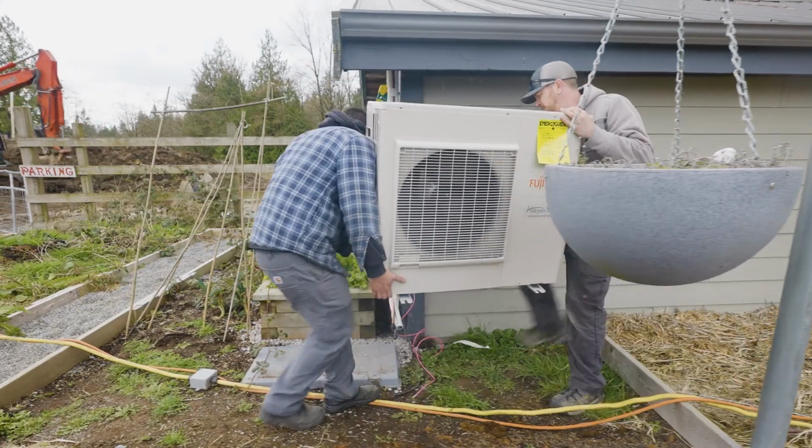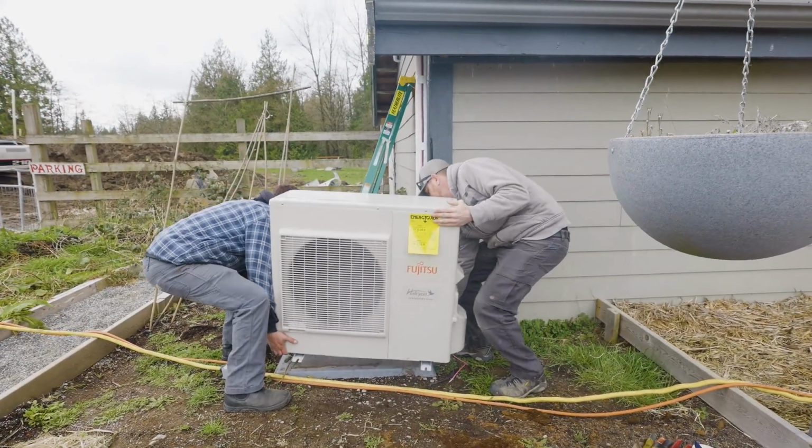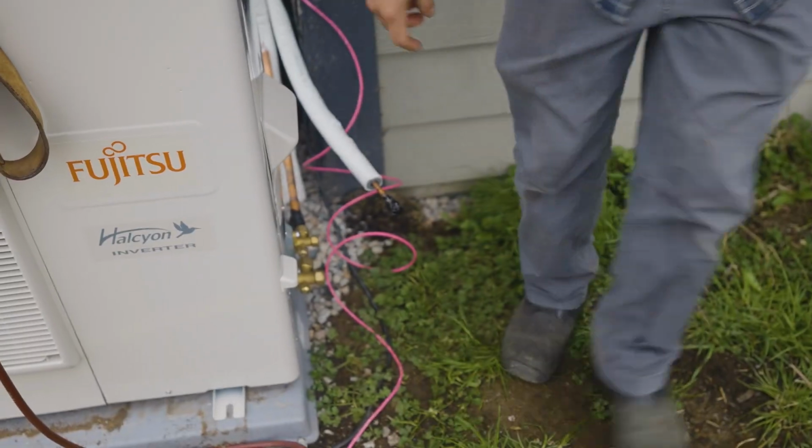Basically, the fan slows down, is that correct? The fan can slow down, and the compressor will modulate based on how many steps it requires from the cooling signal. So it could be running at 20-25%. Correct. And overall, it can be a 30% cost savings by going this route with the inverter technology. And we decided to go with Fujitsu. Correct. Been around a long time, very well built product. Never had very many issues with them.